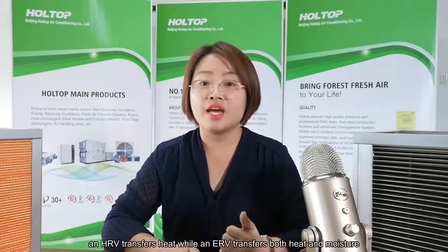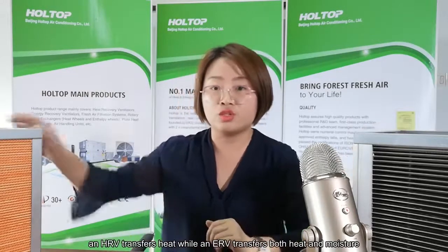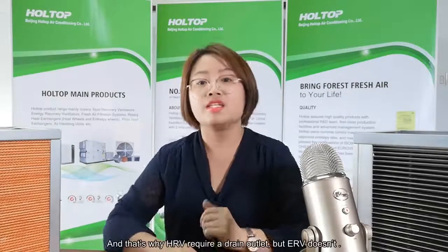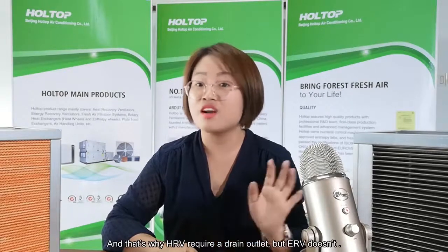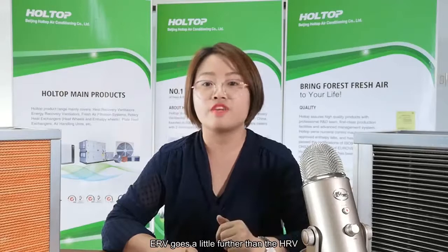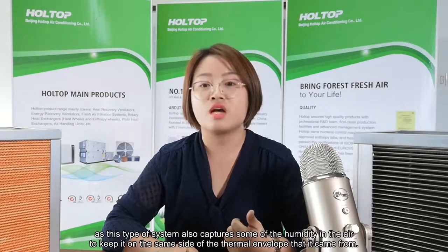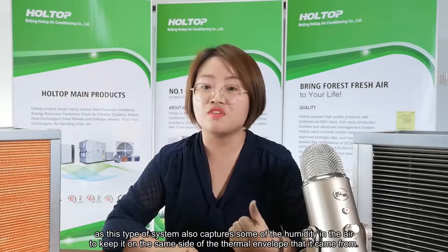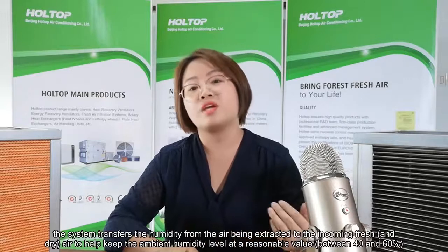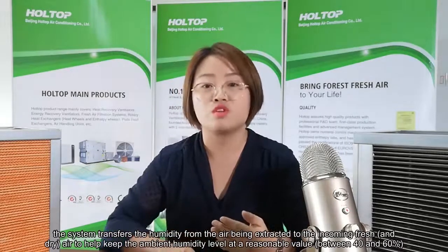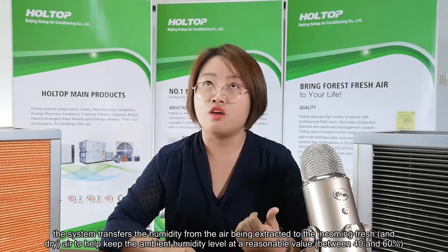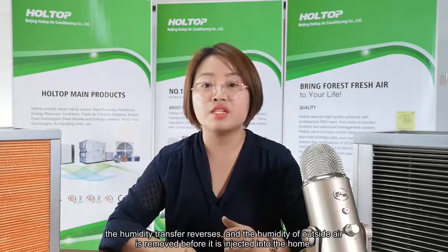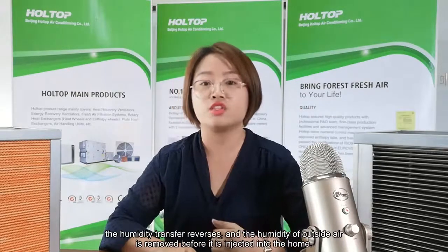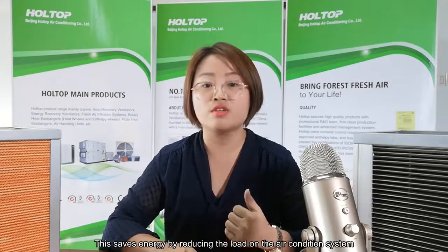So let's put it simply. The HRV transfers heat, and the ERV transfers both heat and moisture. And that's why the HRV requires a drain outlet, but ERV doesn't. ERV goes a little further than the HRV, as this type of system also captures some of the humidity in the air to keep it on the same side of the thermal envelope that it comes from. In winter, the system transfers the humidity from the air being extracted to the incoming fresh air to keep the ambient humidity level at a reasonable value, for example, from 40% to 60%. In summer, the humidity transfer reverses, and the humidity of outdoor air is removed before it is injected into the home. This saves energy by reducing the load of the air conditioning system.